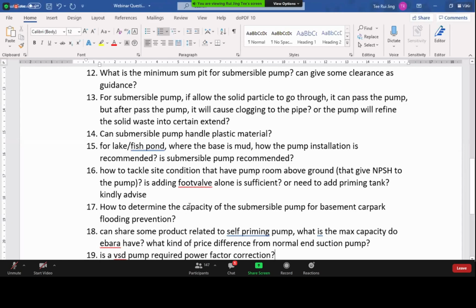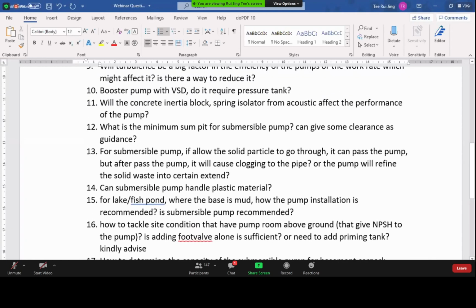So a submersible pump, the motor has to be cooled by the liquid of the surrounding. Basically, if the pump is inside the pit, then whatever liquid is inside the pit is cooling the pump's motor. So it is important, in the relationship between the cooling and when the pump is running, that the pump, as much as possible, has to be submerged.